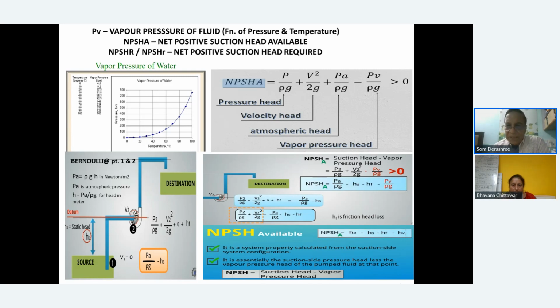Then NPSH available is actually HA, the atmospheric head, plus static lift, minus friction losses, and minus the vapor head is what is available. So hope this is clear. NPSH R, or R, is net positive suction head required. Now this is what is given by the manufacturer. This is what is available with you in this given configuration that your designer has set. That okay, I will keep my pump here, tank will be at the ground floor, and something like that.